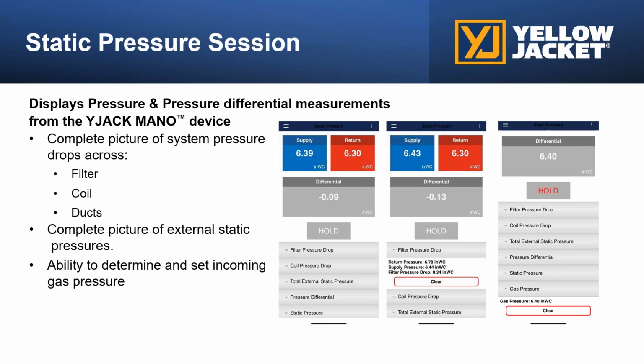So static pressure, this is with the YJACK manometer. It'll give a complete view, call it, of static pressure for filters, coils, and duct pressure. It's a dual port manometer. They have magnets and it goes right onto the duct work.